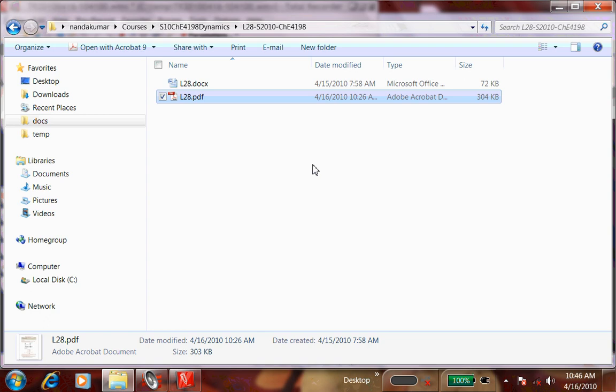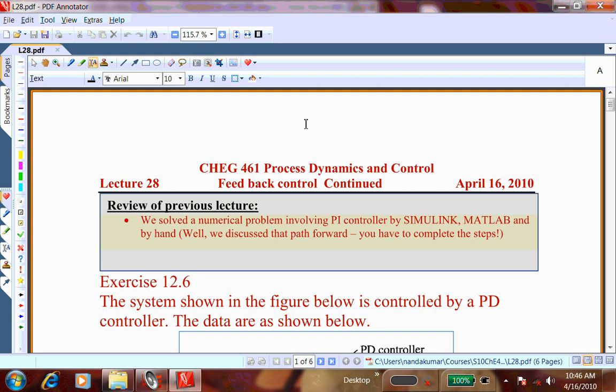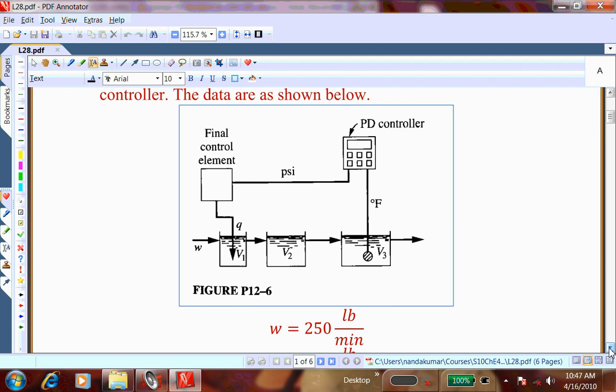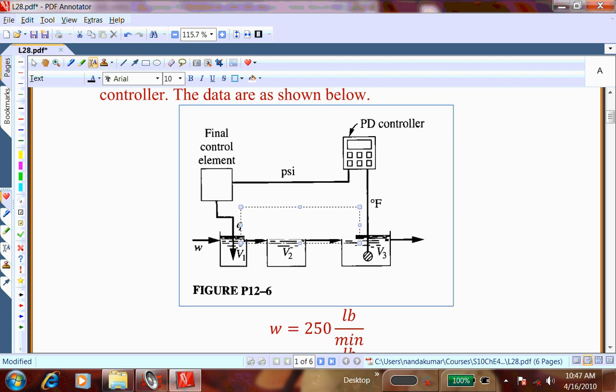When a step change is made from steady state, the controller immediately senses an error. Under steady state there is no error, but when a step change occurs, the controller turns on the heater. That heats up tank 1, but its effect is not felt in tank 3 until the liquid goes through tank 2 and then into tank 3. By the time you sense any increase in temperature in tank 3, tank 1 has already become very hot — that is the cause of the delay. As the temperature rises and reaches the set point, the controller shuts off the heat, but by that time tank 1 has overshot too much.